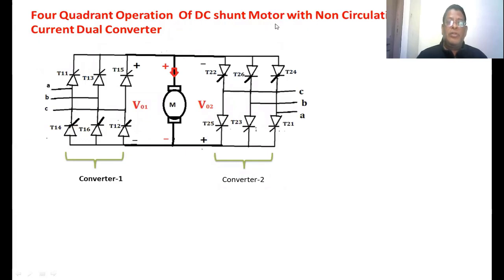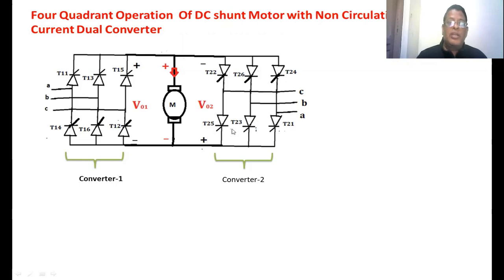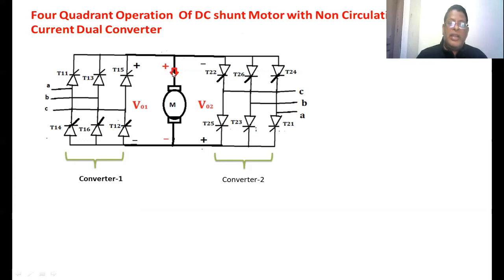For the four quadrant operation of a DC shunt motor using a non-circulating current dual converter, we use two three-phase fully controlled converters. Converter 1 has firing angle alpha 1 and Converter 2 has firing angle alpha 2. Both are connected anti-parallel to the armature of the DC motor. The positive direction of load current and output voltage are indicated; the terminals of Converter 1 (positive upper, negative lower) are shown in red.